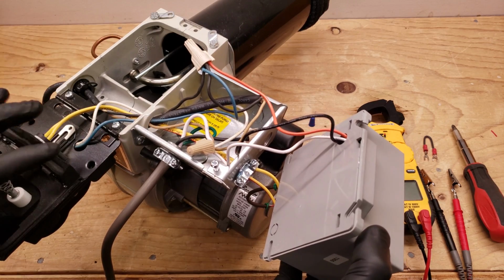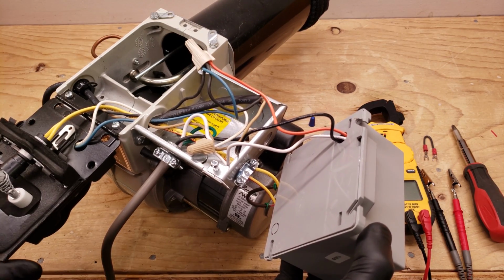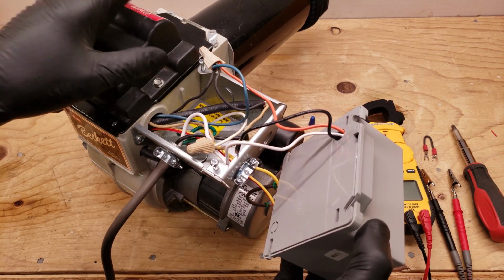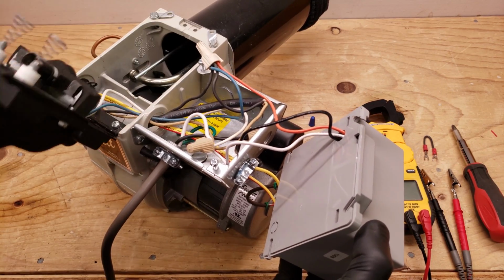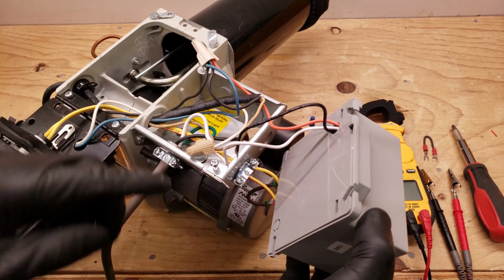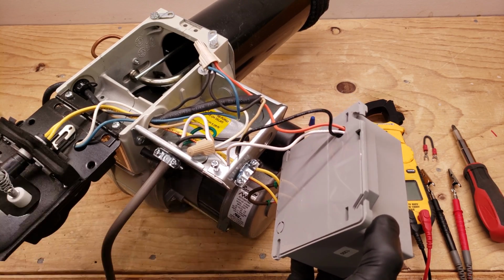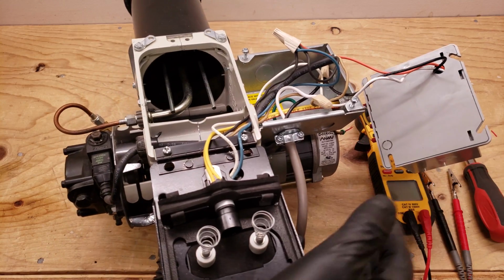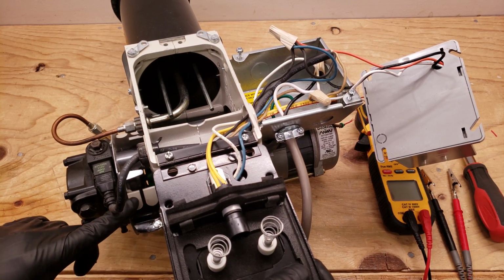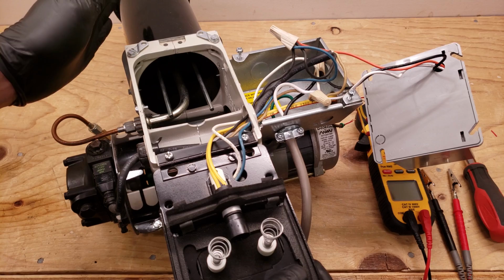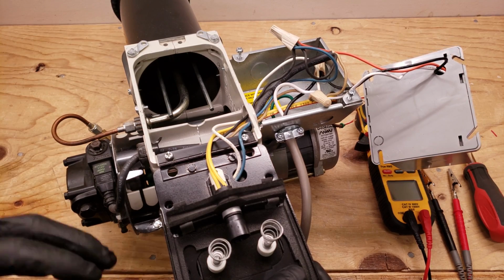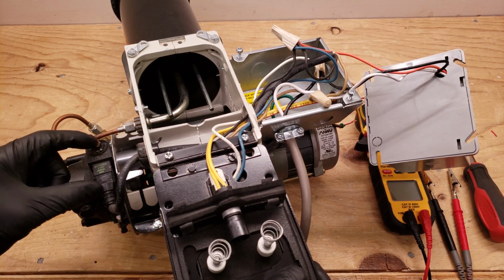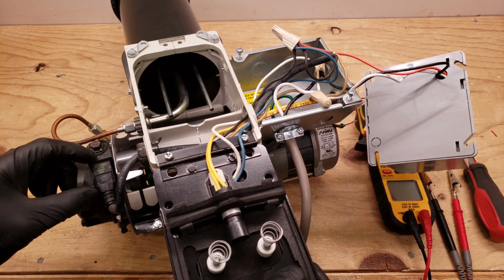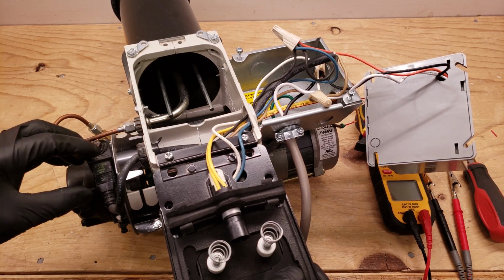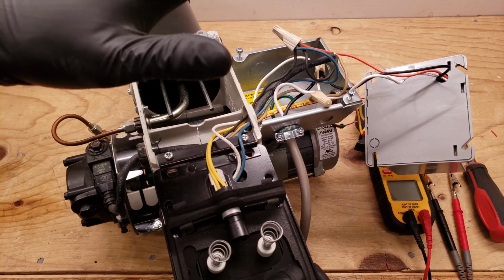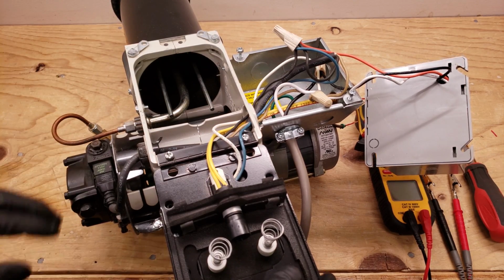So you're sending 120 volts to the transformer, and this could be an electronic transformer or just a standard transformer. It's also sending 120 volts to the motor. So it's turning that on, and when it does that, it's going to be pumping and also sucking the air in and blowing it forward. So that's for combustion. And the third thing it's powering is this solenoid right here. So this is going to stop the oil flow on the pump when the power is no longer there.